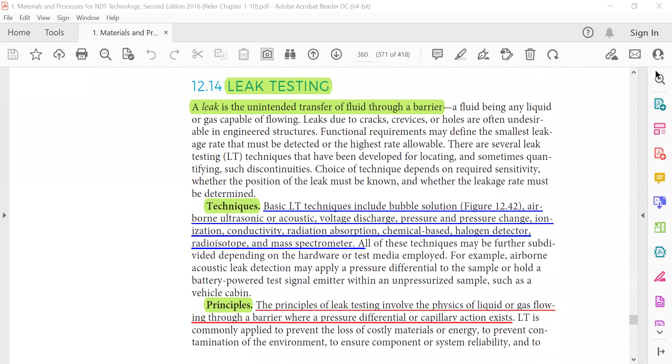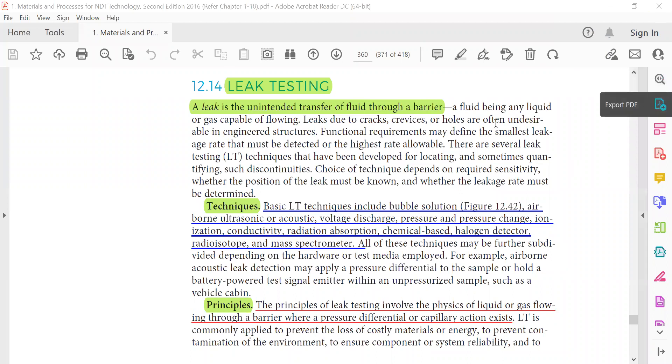Good morning my friends, we will start leak testing. I had one video before, you can see this as extra. In this book, leak testing: a leak is an unintended transfer of fluid through a barrier. Basic leak detection techniques include bubble solution, airborne ultrasonic or acoustic, voltage discharge, pressure and pressure change, ionization, conductivity, radiation absorption, chemical-based, halogen detector, radio isotope, and mass spectrometer.